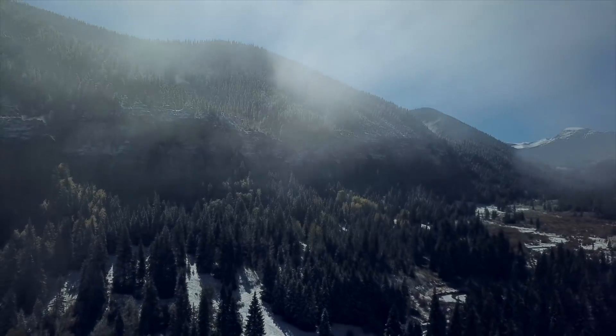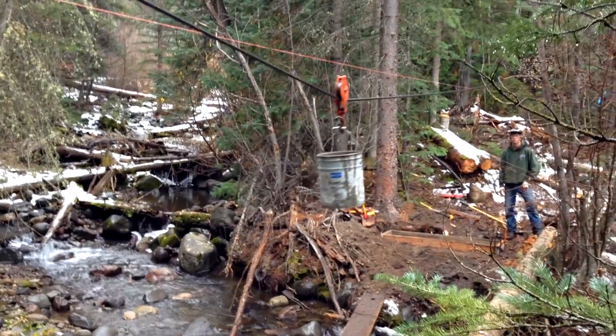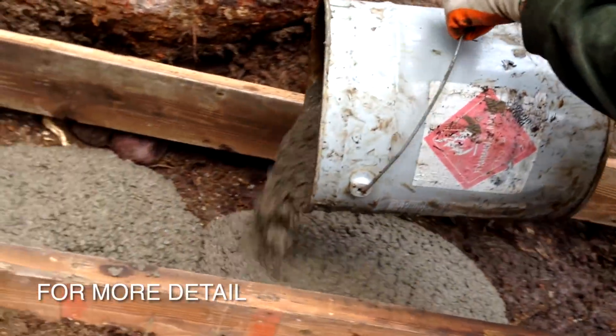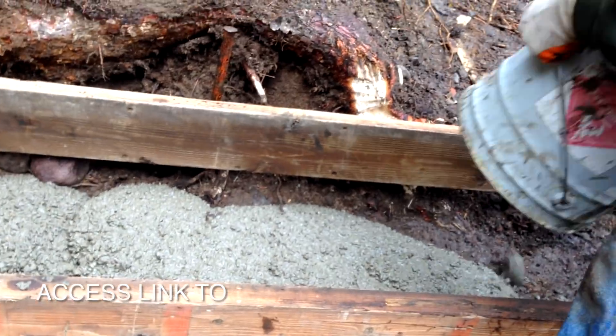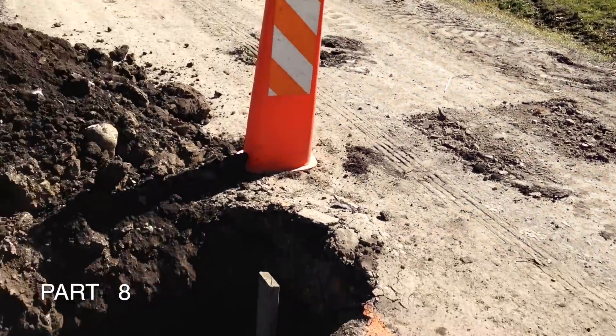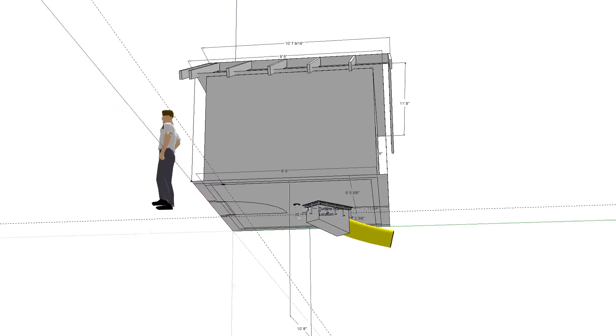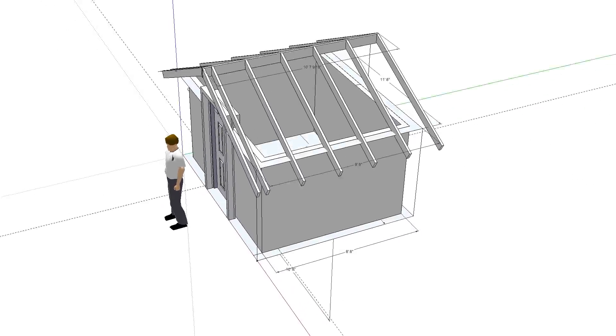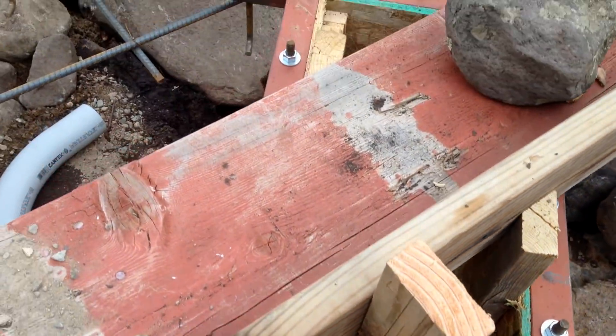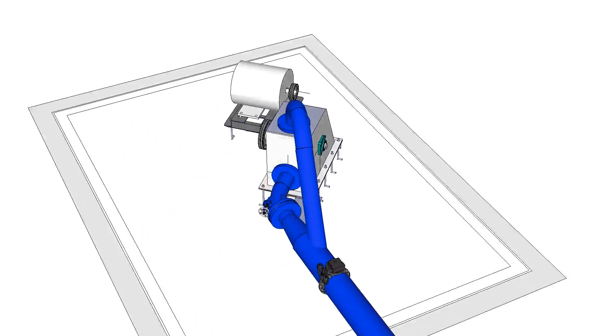It was October and we were starting to get snow, so we needed to move on several fronts. A footbridge was installed over the creek and foundation piers for the bridge were poured using the cable that would support the pipe bridge. We also obtained county permission to dig our transmission cable under the road and buried conduit for that purpose. The powerhouse was designed in great detail with a CAD program so that we were certain how it would all fit together with our existing equipment. The frame to support the turbine equipment would be embedded in the powerhouse slab, and a plan was developed to be able to someday install a second jet into the turbine.